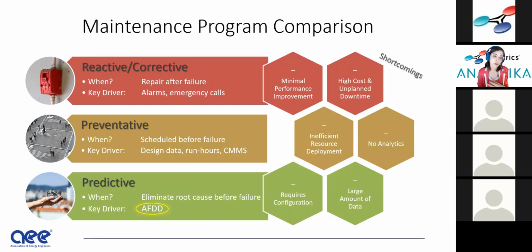And that's important. Sometimes in a preventative maintenance program, you might be fixing valves and things like that. But maybe you're not addressing issues with loop tuning that are causing those valves to fail from the beginning. So that's what I mean by root cause. Really what the analytics software allows a site to do is to see the absolute root cause of something, whether it's a control sequence that's wrong or whatnot, and then eliminate that so that this failure doesn't keep on continuing to happen over time. So the key driver for predictive maintenance is automatic fault detection and diagnostics, and that's what we're going to be talking about next.